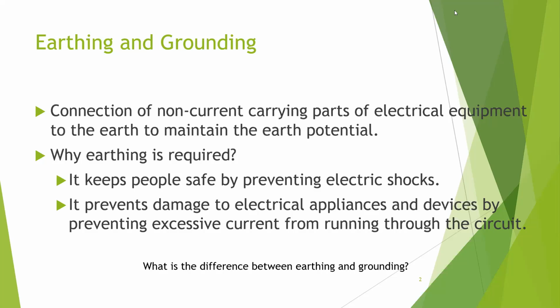Okay. So earthing is connection of non-current carrying part of electrical equipment to earth to maintain the earth potential. So you know, in our installations, let's say you have an oven connected to a socket outlet in your home. The enclosure of the oven is metal, right? So that part is a non-current carrying part. So we should connect those parts to earth. So that is what is meant by earthing.